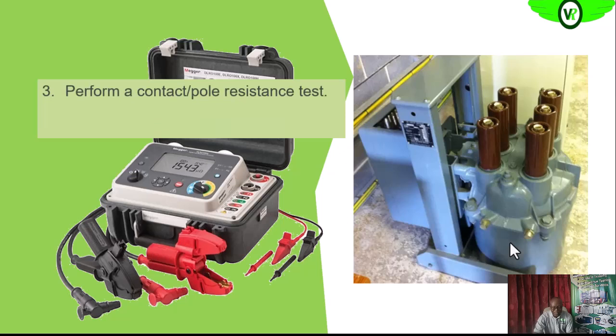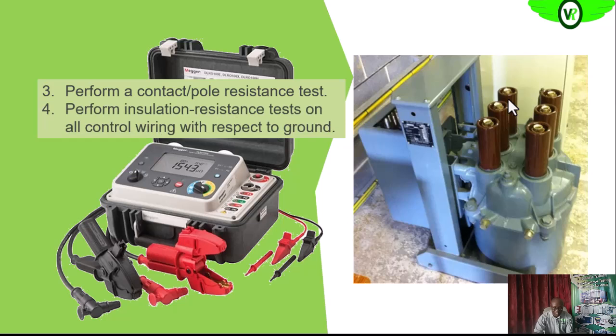So the next test, as we said before, we want to perform the contact pole resistance. We can use this low resistance meter like this when the contacts are closed, so we can probe these two terminals. Okay, that will give us the effective resistance. So we'll do it for line 1, line 2, line 3 to give us the resistance across the poles, as we said earlier before. Then on the control wiring, we want to also carry out the insulation resistance to ground, but we need to be very careful. We need to follow the instruction of the manufacturer in case we have sensitive digital devices in that control circuit, so that we do not go and damage them.